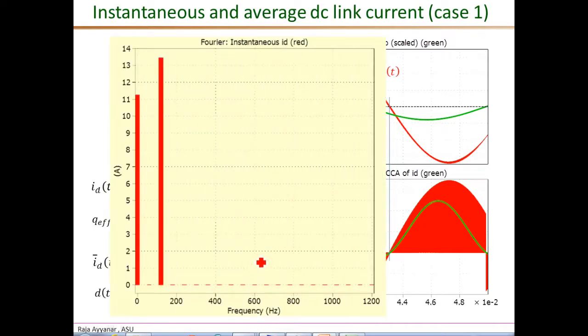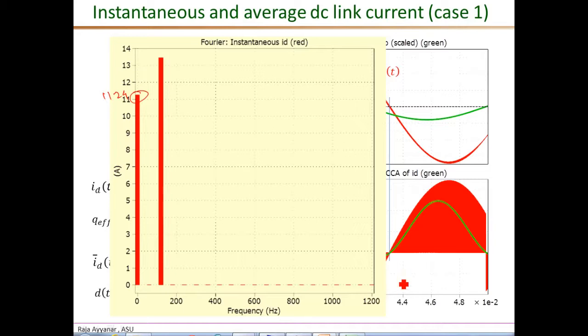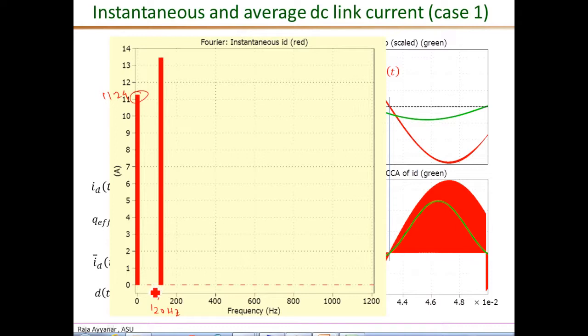Looking at the FFT of the instantaneous DC link current, we can clearly see the DC component and the two-times line frequency component. The DC component at zero frequency is 11.24, and this is shown up to about 1200 Hz. The 120 Hz component has a value of about 13.5, which matches exactly with what we calculated. There are no other low-frequency components, and specifically there is no 60 Hz component in this DC link current.